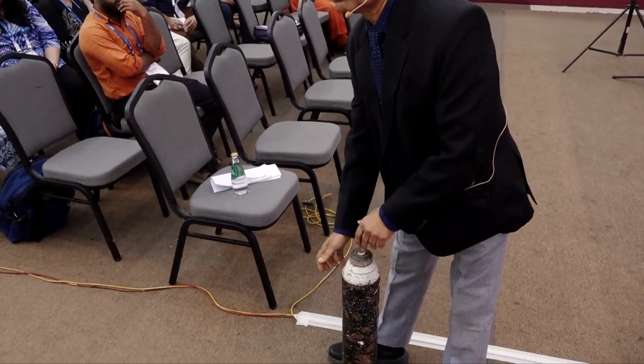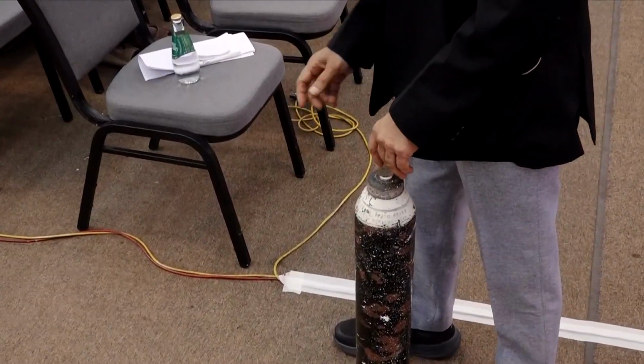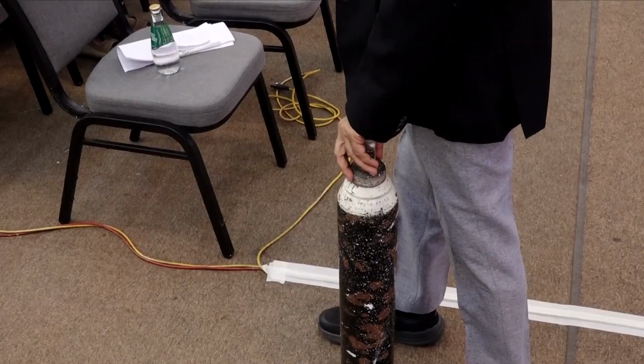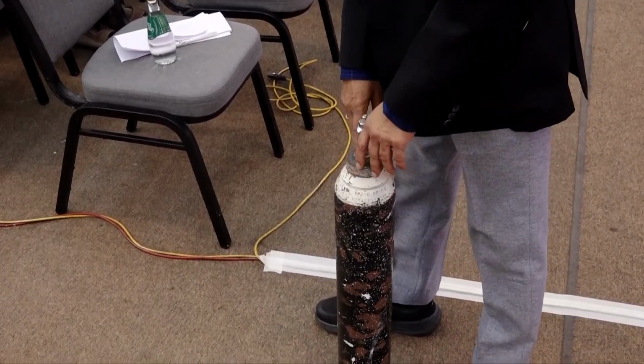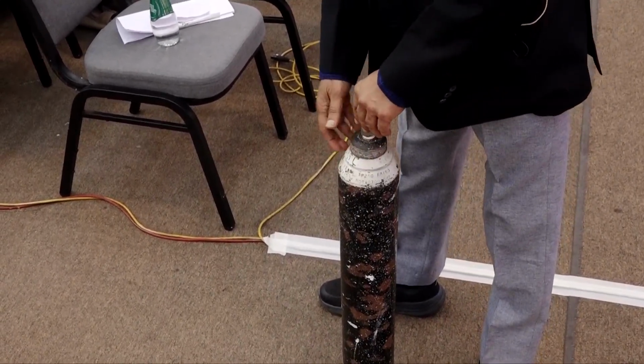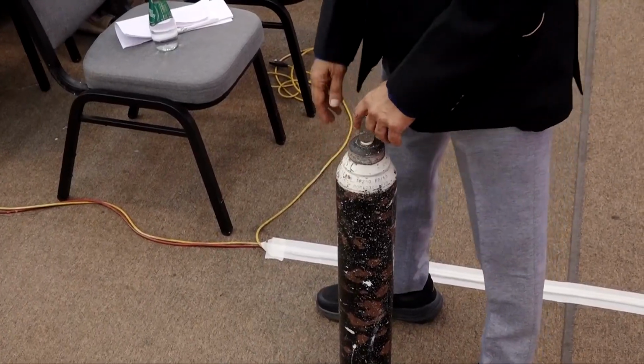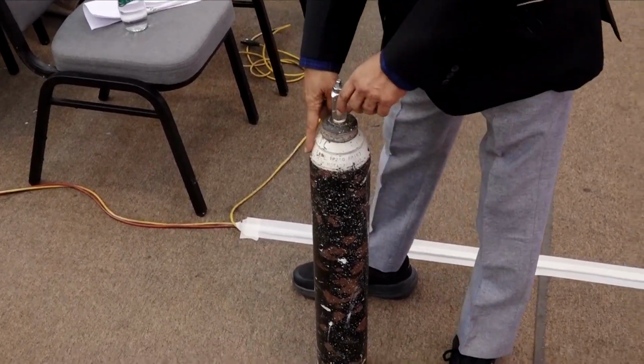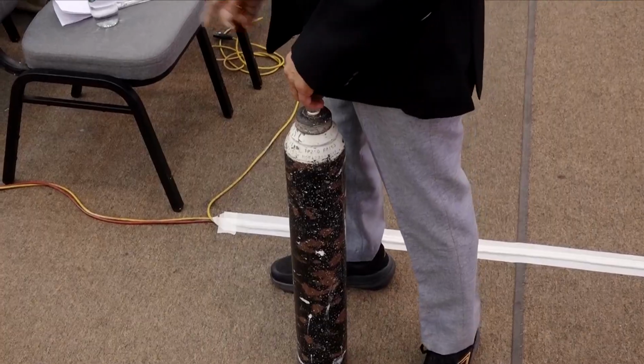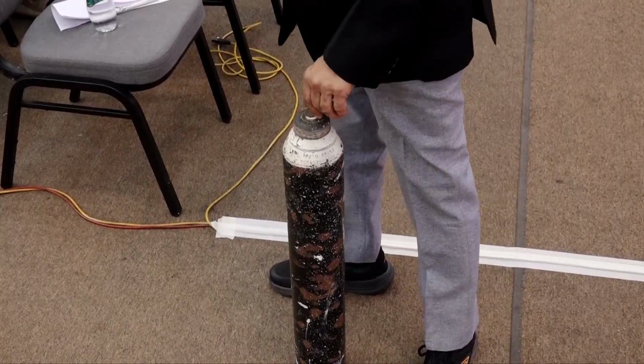All medical grade cylinders have a white body. Only from the shoulder can you recognize them. The shoulders are color coded, like oxygen is white and white, nitrous oxide is white body and blue shoulder. Plus a capital N is written on the shoulder. That is the new international color coding.